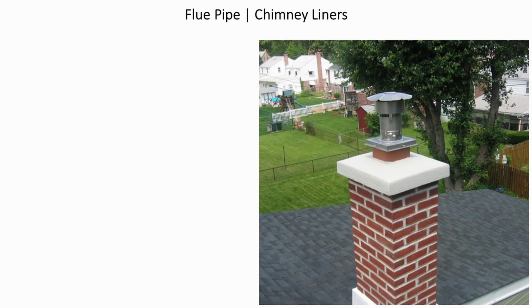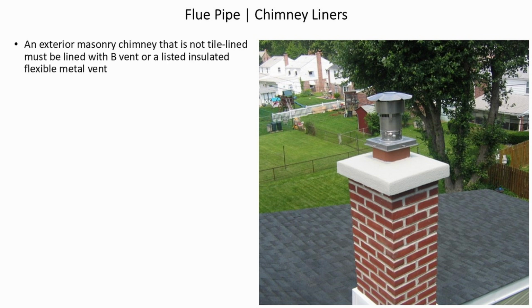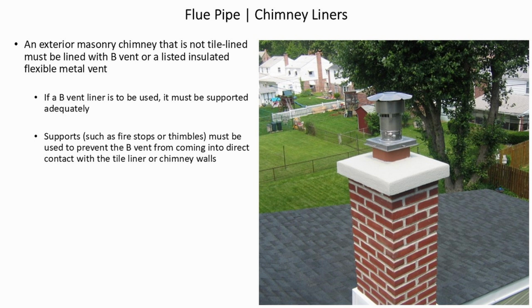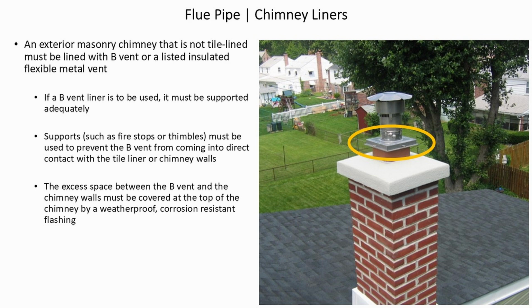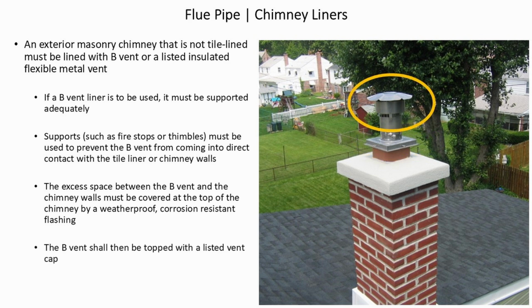Flue pipe with chimney liners. An exterior masonry chimney that is not tile-lined must be lined with B-vent or a listed insulated flexible metal vent. If a B-vent liner is to be used, it must be supported adequately. Supports, such as fire stops or thimbles, must be used to prevent B-vent from coming into direct contact with the tile liner or chimney walls. The excess space between the B-vent and the chimney wall must be covered at the top of the chimney by a weatherproof, corrosion-resistant flashing. The B-vent must be topped with a listed vent cap.